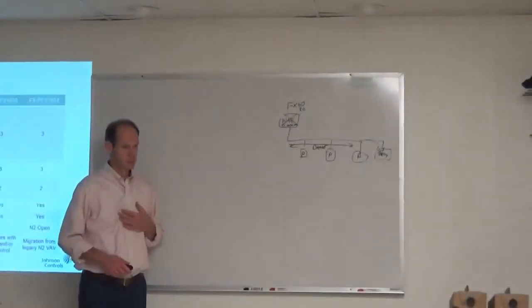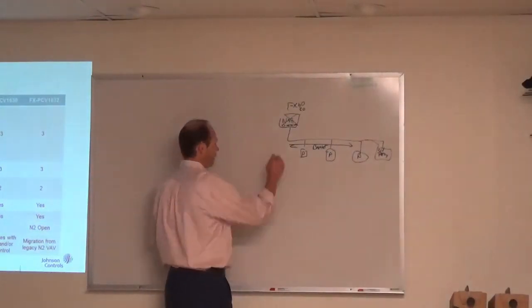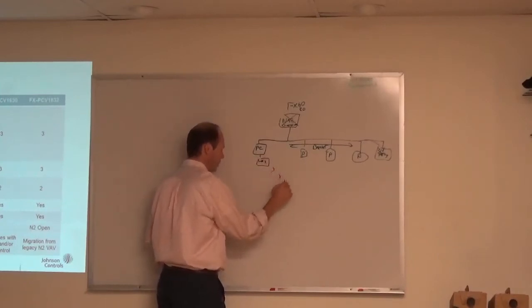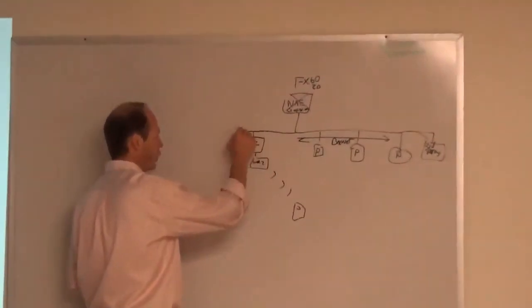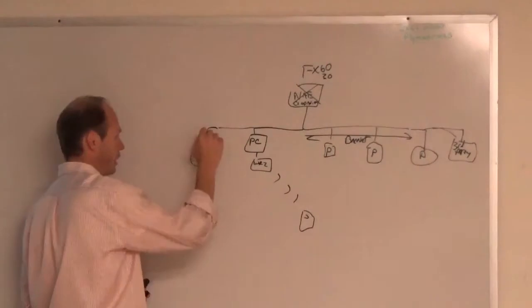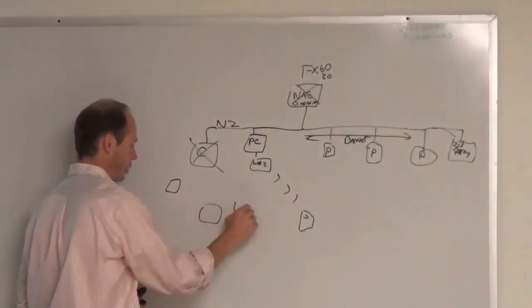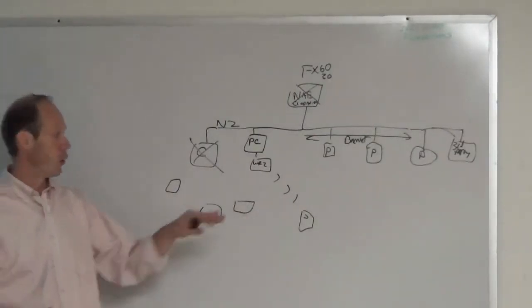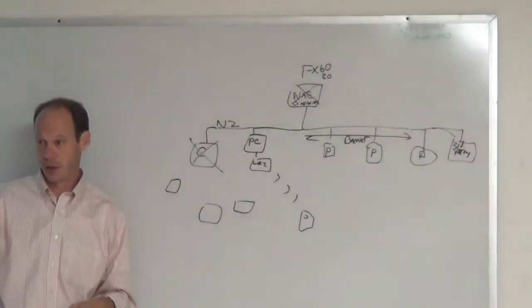I'm going one step further. If you do that, is the wireless still available in N2? Wireless is available on N2 for this part. So if I have a PCG controller, I can put a WRZ and do wireless communication to a sensor. I can't do a coordinator like this. This is an N2 bus. I can't put a coordinator and a controller and a controller and a controller. I can only do the wireless sensor bus, not N2. So all of the wireless stuff we're talking about, wireless sensor bus and communication bus, those are all with the white controllers, the PC controllers. It doesn't work with N2.